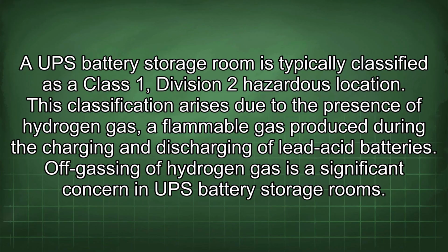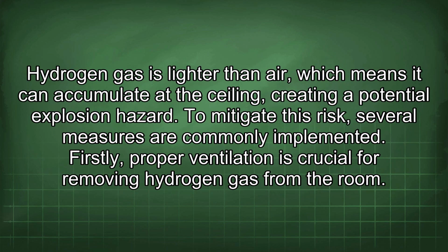A UPS battery storage room is typically classified as a Class 1, Division 2 hazardous location. This classification arises due to the presence of hydrogen gas, a flammable gas produced during the charging and discharging of lead-acid batteries. Off-gassing of hydrogen gas is a significant concern in UPS battery storage rooms. Hydrogen gas is lighter than air, which means it can accumulate at the ceiling, creating a potential explosion hazard.